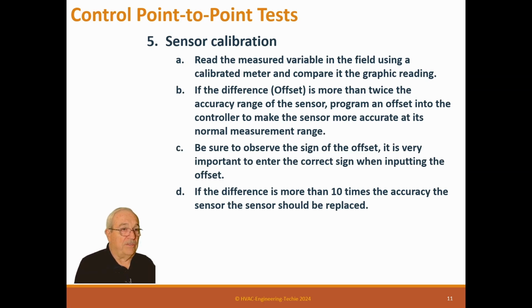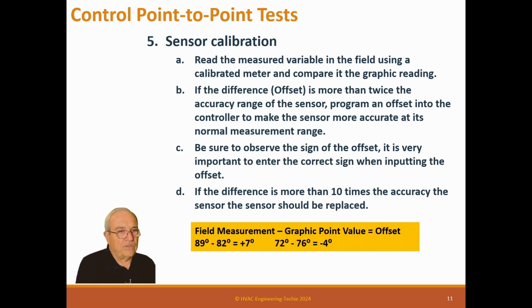That's pretty bad. If it's off by 40 degrees, now thermistors are pretty good because thermistors are the cheapest ones, little bitty ones. They don't go off by a few degrees. If it says 1,000 degrees, it's got a problem. You need to change it out because they go really large. So here's the field measurement again.